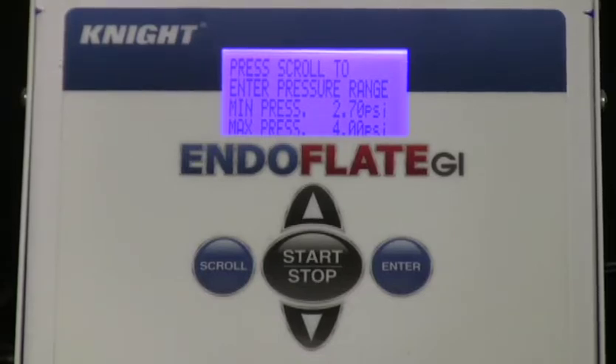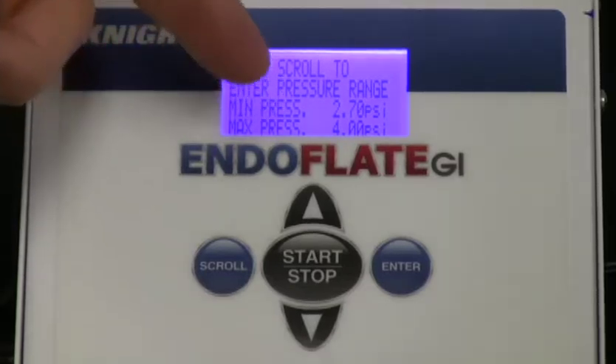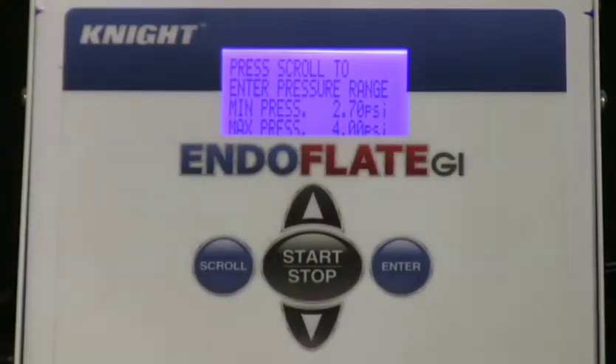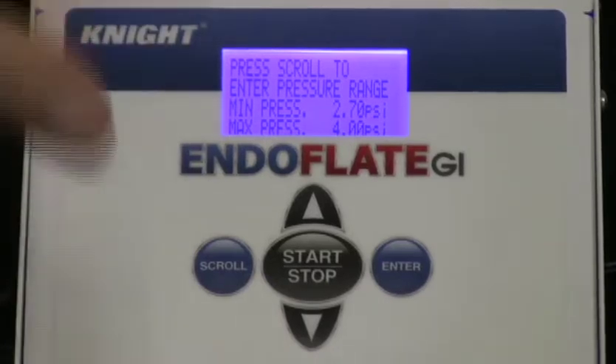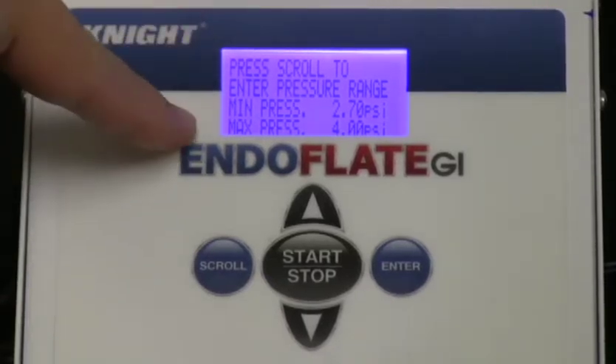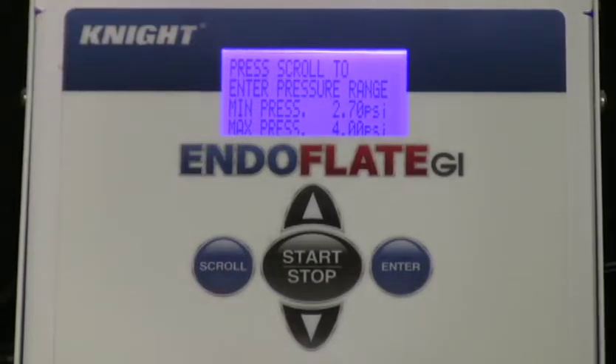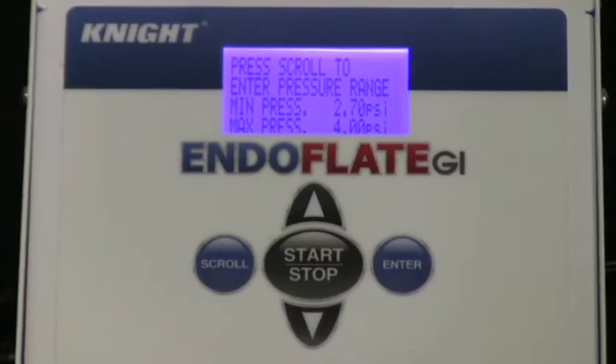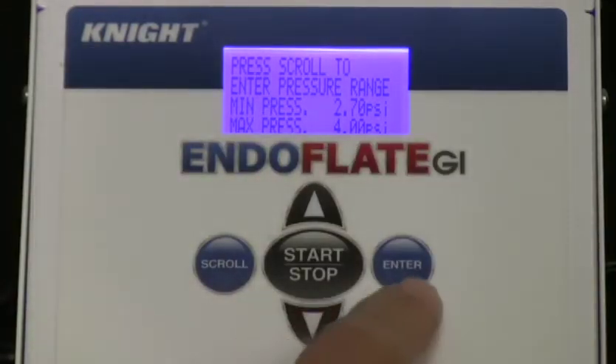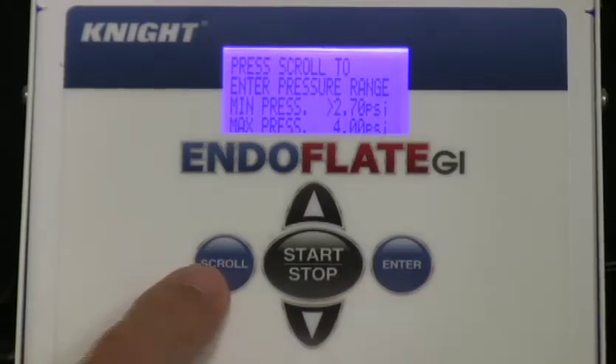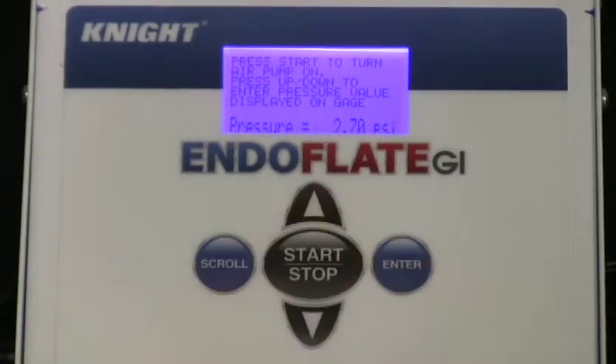The typical endoscope is going to be able to sustain an inflation pressure far higher than what the pump in here can produce, so we don't have to worry about damaging the liner in the scope. But it's a general reference. That's what you're going to get out of the box. Now you can change what that range is. I can't advise you right now on any other sources of information for what that should be, but we'll keep everybody informed and have in the instruction manual any references from the OEMs about what these levels should be for setting in the field, beyond what we put in at the factory. Okay? To make the changes, again, you just hit scroll, and you can go up and down. Very simple. Hit enter when you've got the values that you want.